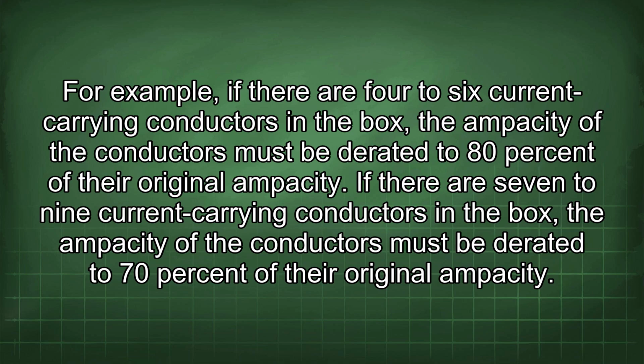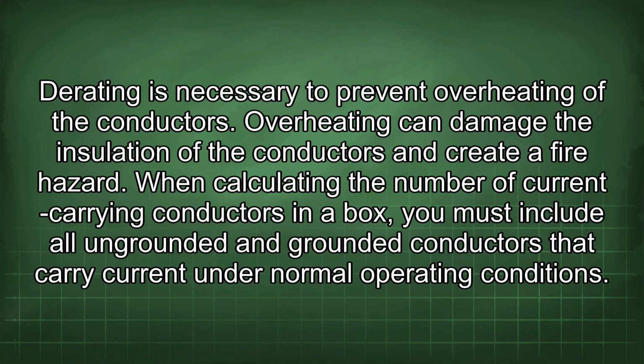If there are 7 to 9 current-carrying conductors in the box, the ampacity of the conductors must be derated to 70% of their original ampacity. Derating is necessary to prevent overheating of the conductors. Overheating can damage the insulation of the conductors and create a fire hazard.